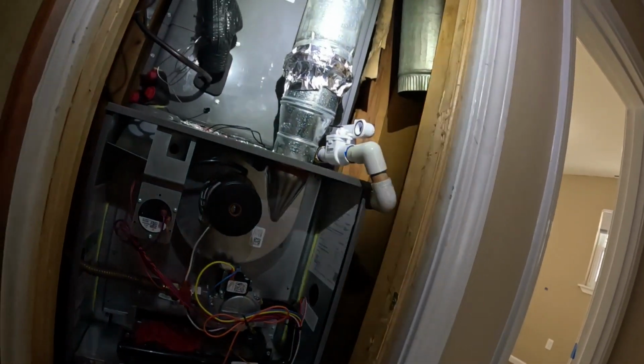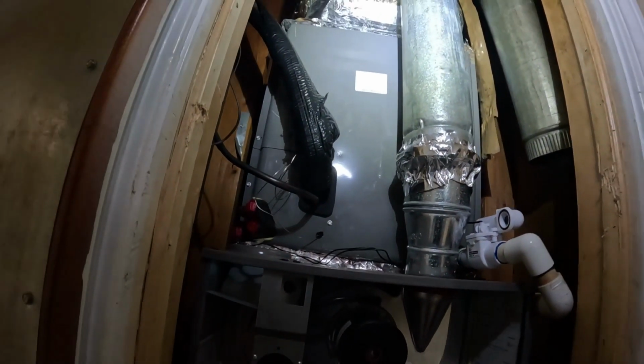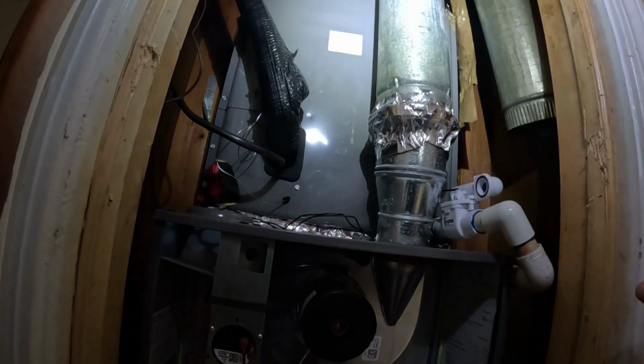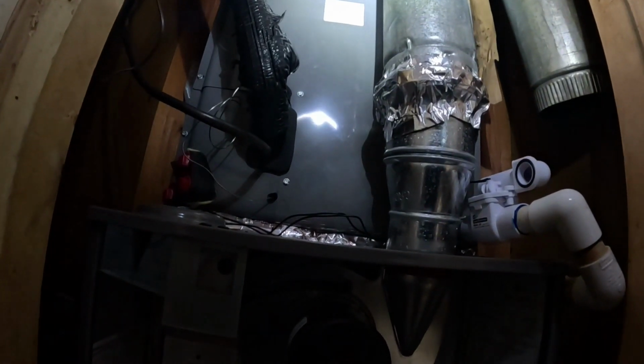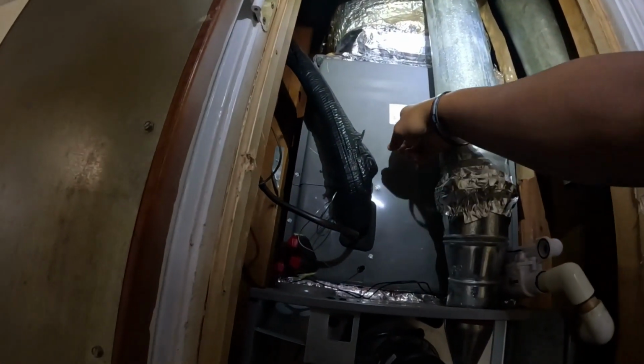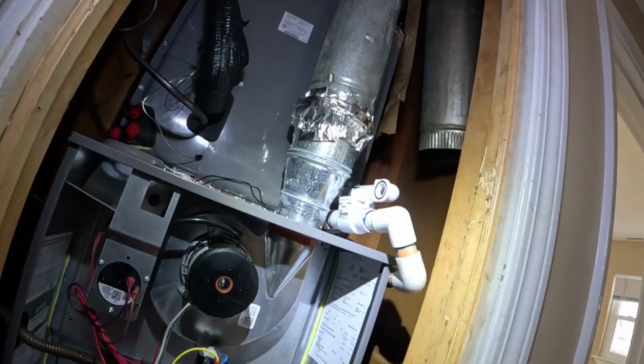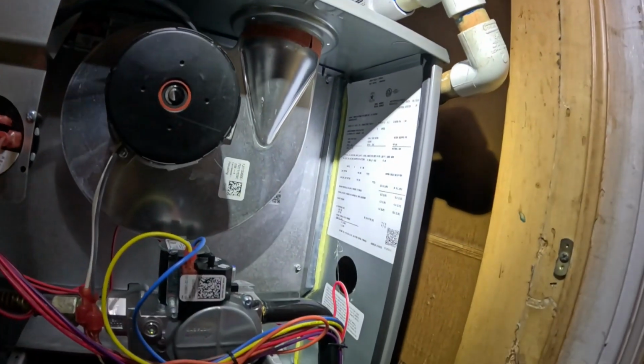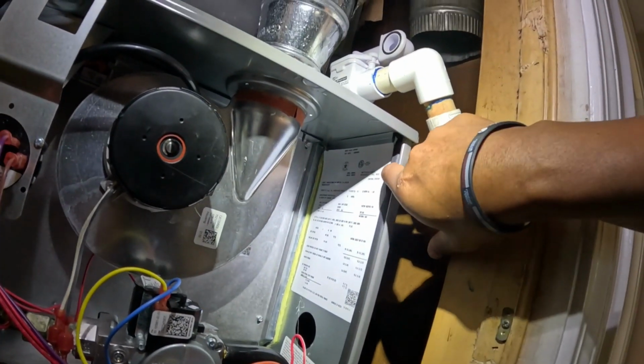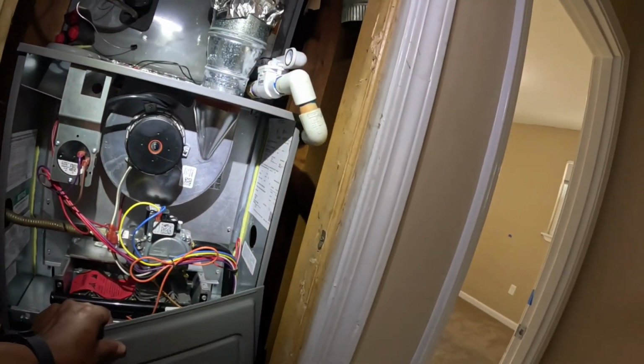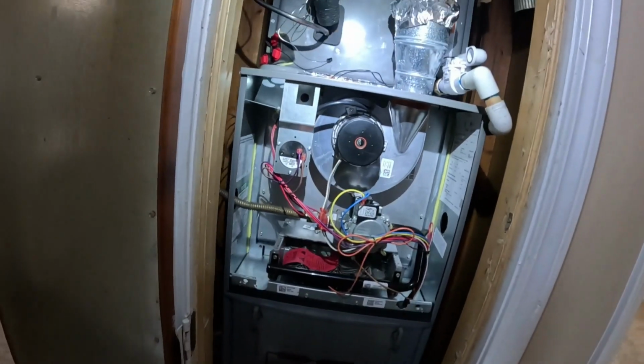This closet is very tight knit, and it was a 2.5 ton outside on the condenser. I believe I might have to recheck it. But this evap coil says it's a 3 ton RCFZ 3717 up there, and it's a 2023 manufacturing date. The furnace inside is a 2024, but man, pretty clean in here still. Pretty darn clean in here still.